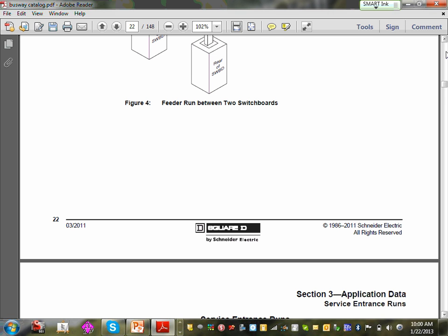It's when you get the order that it becomes much more complicated, because say the switchboard's in the basement facing this way, and the piece of equipment you're feeding up on the fourth floor is over here feeding this way. Well, now you got ABC, ABC, so you have to make sure that this piece of gear is built right, CBA, N, versus NABC here as a connection so that the phasing's built right.